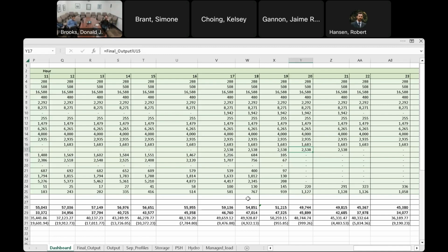I had a similar question to Noah, just diving into these energy storage numbers here and the 6 hour sort of thing. I don't think conceptually there's anything wrong with saying, look, the batteries are available over the 6 hours, which is what I think you're trying to do on the Sep_Profiles tab. But my concern is I'm wondering how much available energy you're limiting to. There's really 2 constraints in my mind. There's the total available energy, say in a cycle over a day.